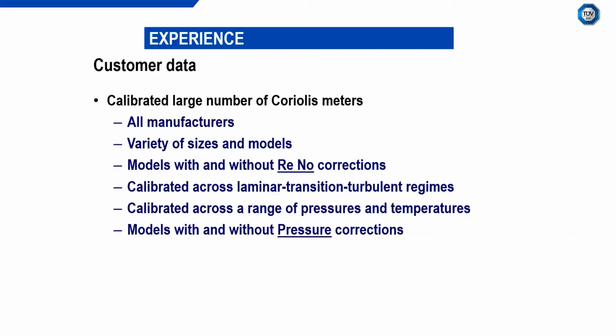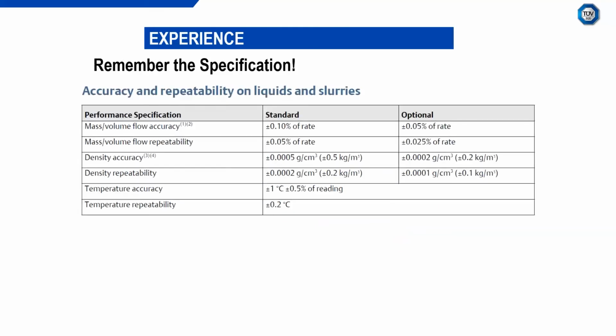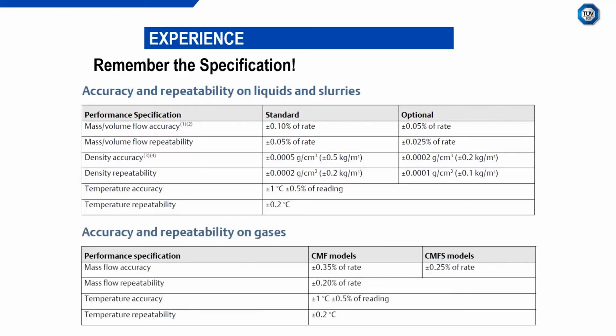So, Coriolis meters, typically known as being 0.1% devices for liquid, 0.05% for the elite devices. So the best meters might achieve 0.05%, at least that's their specification. But by and large, most Coriolis meters aim for 0.1%. And I would also say that the majority do achieve that in the linear range at certain conditions with corrections applied. Also for gas, one of the real benefits of Coriolis meters compared to other devices is that the same Coriolis meter can be used for measuring liquid and gas.